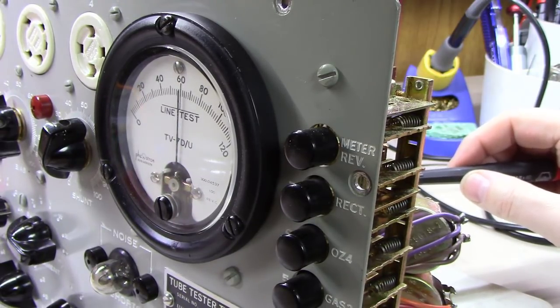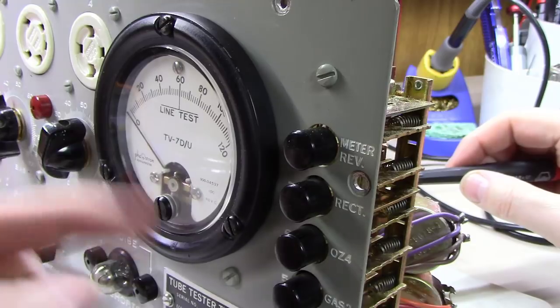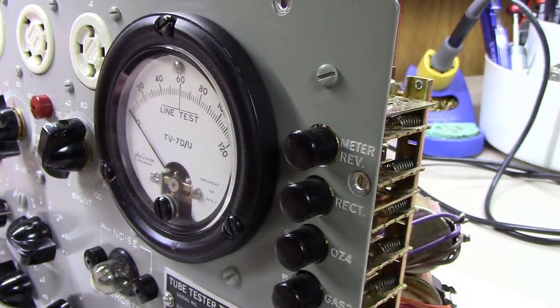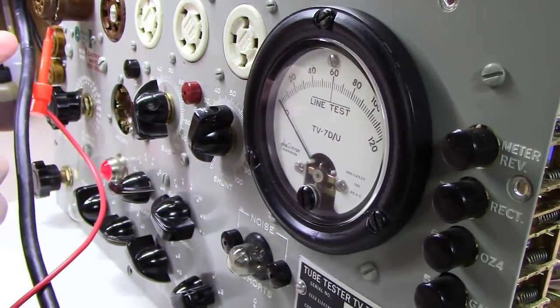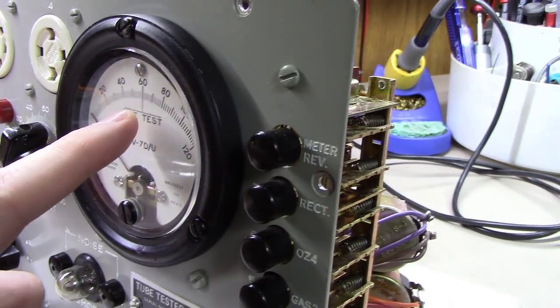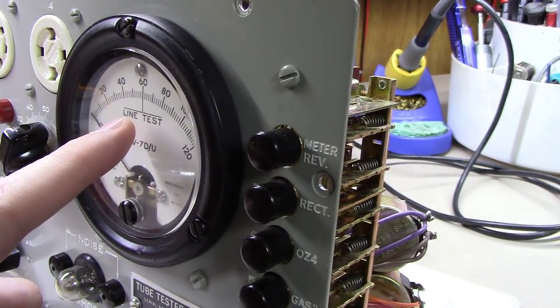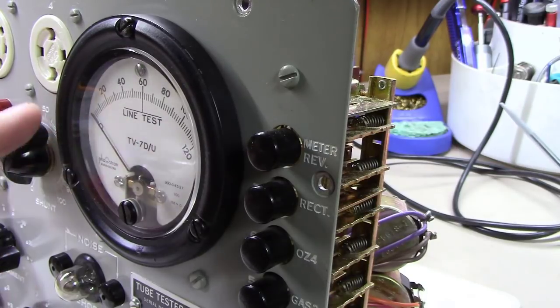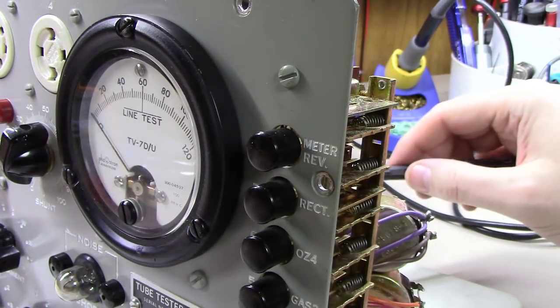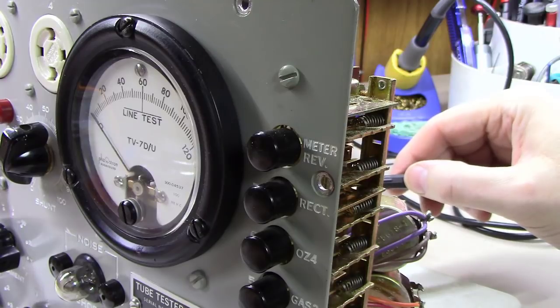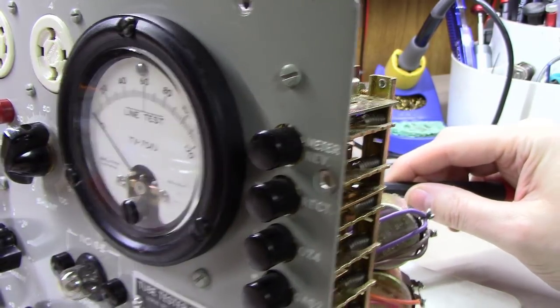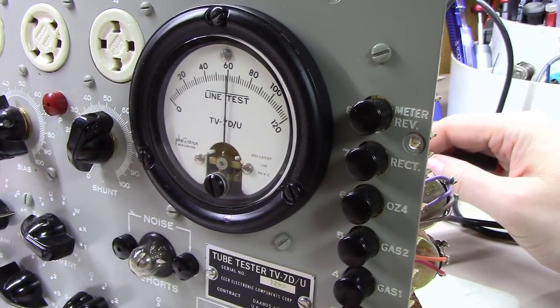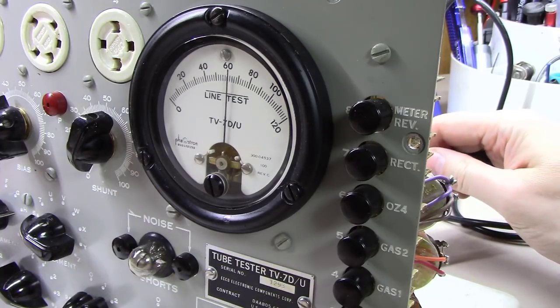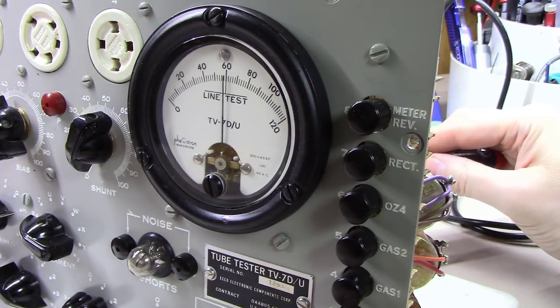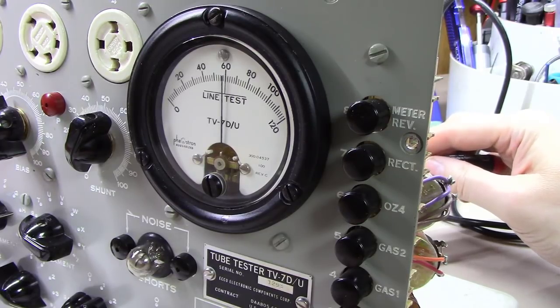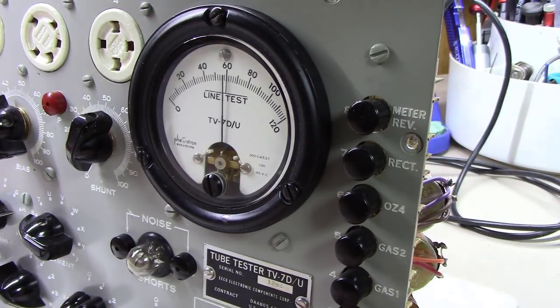What this R134 adjusts is not the voltage to these pins over here of the socket. What it adjusts is where your line set is relative to the voltage being applied to this thing. So let me give you an example here. If I push the line test button, and let me spin this around so you can see it well. Right now it's on 60, but if I turn this a little bit, it'll go one way or the other.